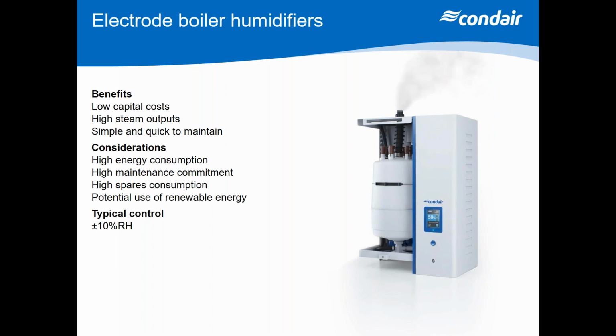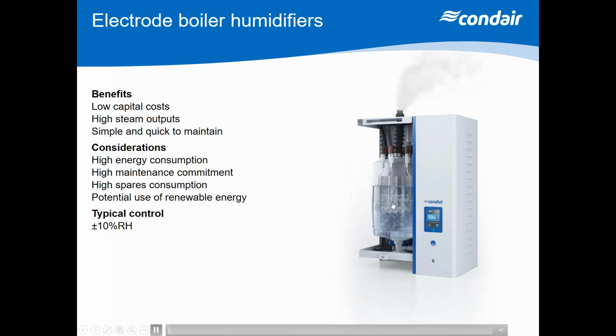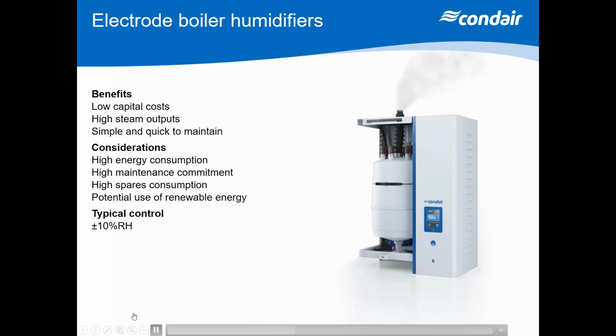The other thing to consider is the water quality. Because as we produce steam inside this cylinder, any minerals will get left behind and will form a scale on these electrode plates. And eventually, these electrode plates will scale up with so much scale and will deteriorate. And eventually, the unit will say, oh, do you know, I'm so full of scale now, I can't produce steam anymore.